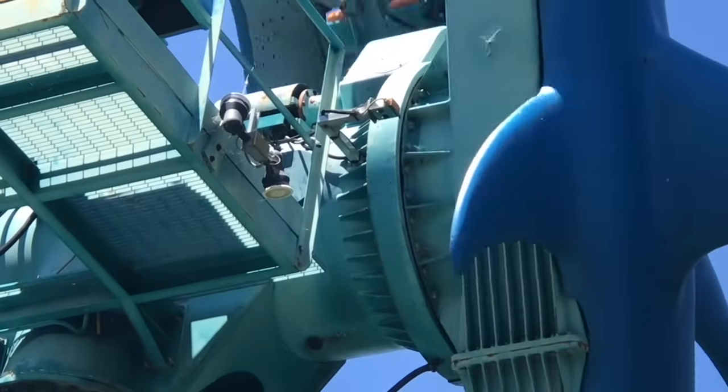So what would happen is that they would turn the switches out of sequence, and then they would hit the platform and tell the platform to go down because it was too close to the ride, so it had to lower first. And then once the platform got all the way down to the bottom and the DC drive enabled, as soon as that drive enabled, it would fault out with a lap bar fault. So we would get those all the time, but we had one operator out there that just continued to do it time and time again.